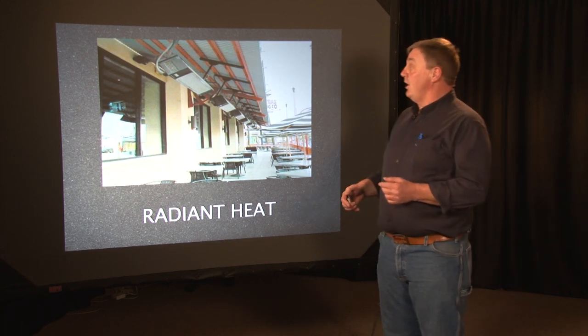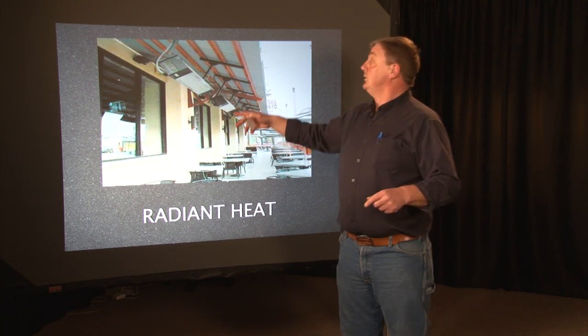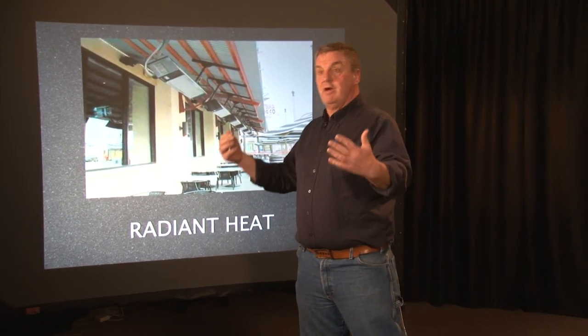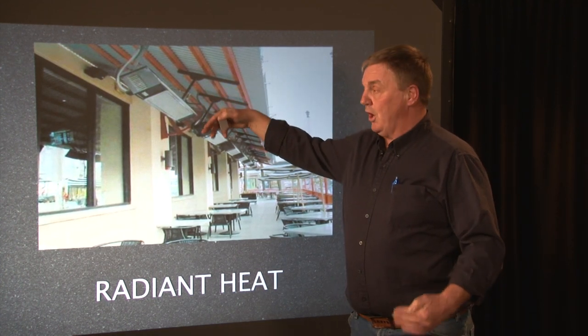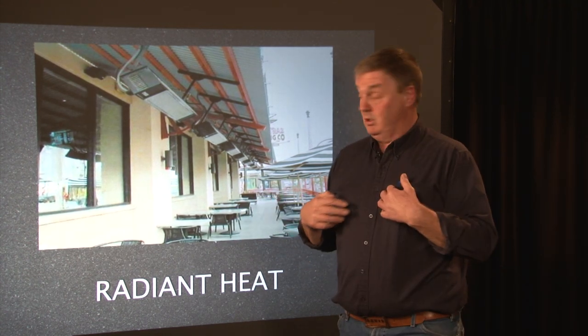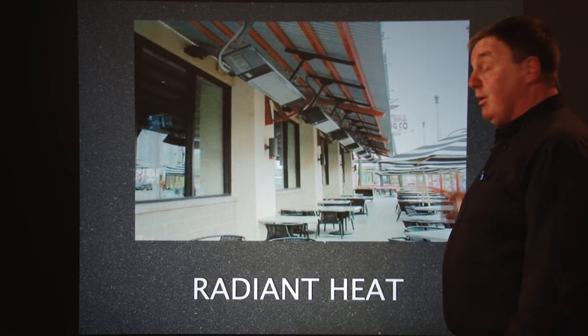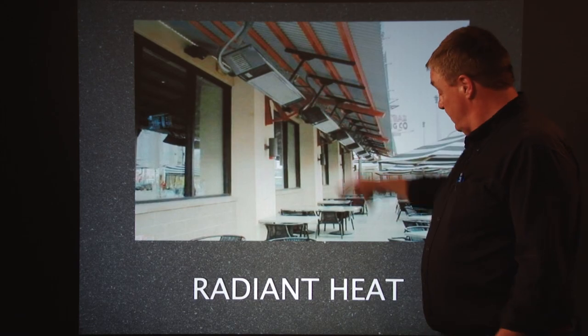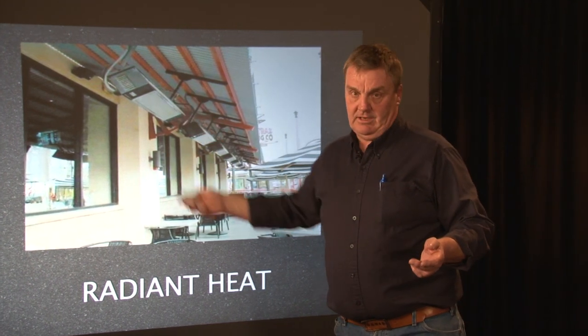This is another type of radiant heat — infrared heat. This is a low intensity infrared heater, used on a patio, in a restaurant, or a club. They're usually gas fired with an electrical spark. They're called infrared because they glow red. The idea of low intensity is that they don't have to be mounted quite so high. The heat is pumped down to the floor and transferred to whatever's there — whether it's you, the furniture, or the floor — and then you or the floor radiate heat, generating warmth throughout the whole area. The recommended height is around 10 feet for them.